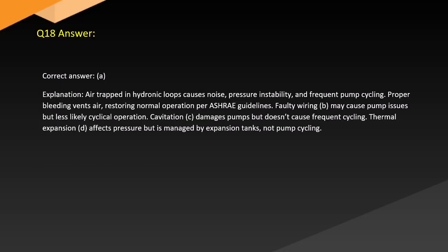Answer. Correct answer, A. Explanation. Air trapped in hydronic loops causes noise, pressure instability, and frequent pump cycling. Proper bleeding vents air, restoring normal operation per ASHRAE guidelines. Faulty wiring, B, may cause pump issues but is less likely to cause cyclical operation. Cavitation, C, damages pumps but doesn't cause frequent cycling. Thermal expansion, D, affects pressure but is managed by expansion tanks, not pump cycling.